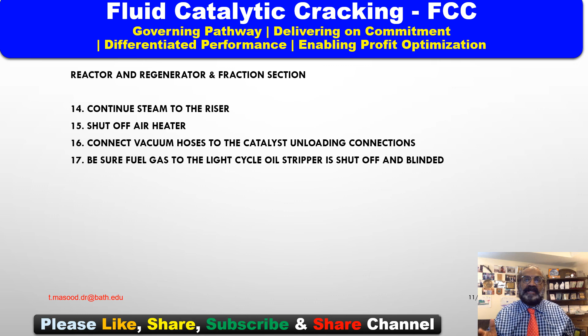Okay, number 18. When it is felt the reactor and the main column are hydrocarbon free, decrease the risers and the main column bottom steam flows until only a trace shows at the vent located at the reactor vapor line blind. Remove the blind in the reactor vapor line vent and install a blind at the main column inlet. After the main column inlet blind is installed.